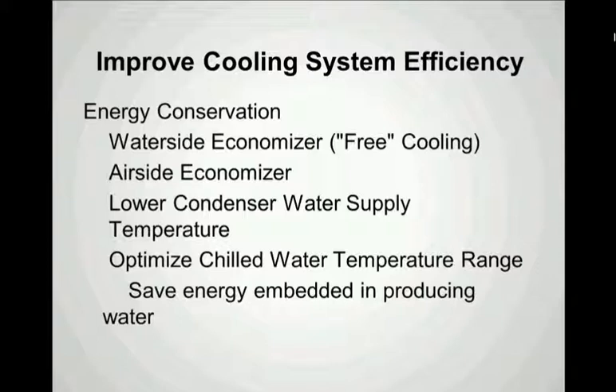A 1-degree drop in condenser water temperature represents an approximate 1 percent improvement in chiller efficiency, so we need to make sure we're operating the tower to maintain as low a condenser water temperature as is permissible by the chiller manufacturer. Also, optimizing the chilled water temperature range helps conserve energy by taking some of the load off the chiller, and by reducing our water consumption, we also save the energy that's embedded in producing the makeup water used in the cooling tower.